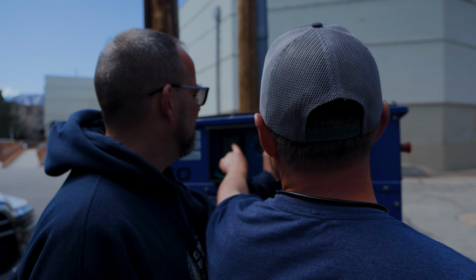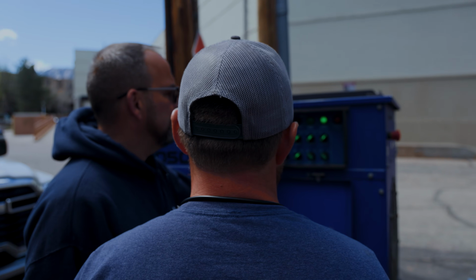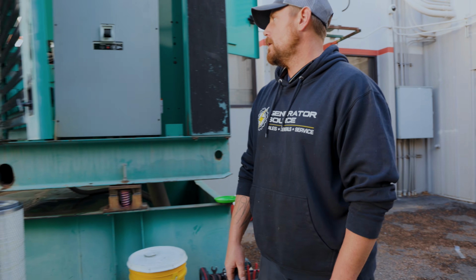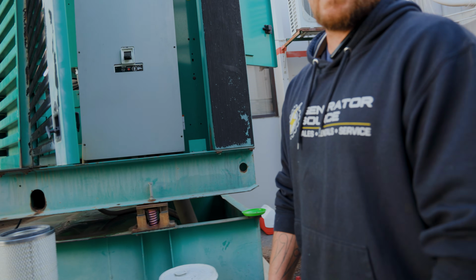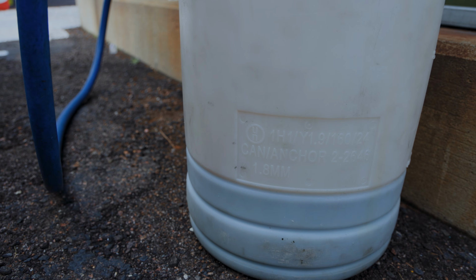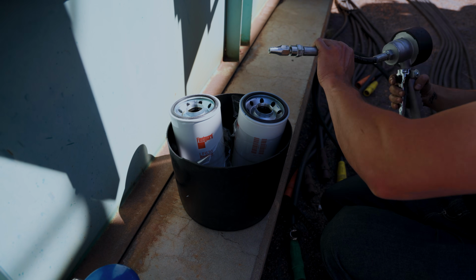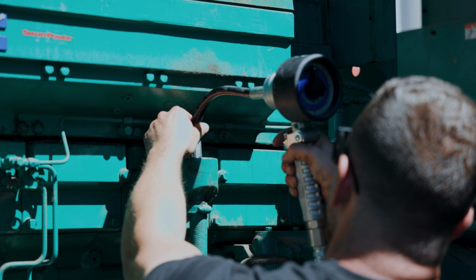Once the load bank test is done, we do what's called a hot oil change. Do everything but the oil first. Gotcha. The oil and oil filters will be last. We feel that we're getting all of the gunk, the carbon buildup out of the oil and out of the generator, out of the system. It's kind of like giving your car a tune-up, you know. It's basically at its best at that point.